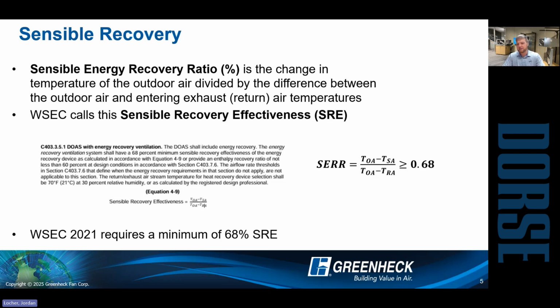Basically, you can see the equation. It's the exact same equation as ERR, just instead of looking at enthalpy, now we are looking at temperatures. So the change in temperature of our supply air over the change in temperature of our return air. And Washington State does have a higher minimum recovery if you're going to focus on sensible recovery. That's 68% versus that 60%.